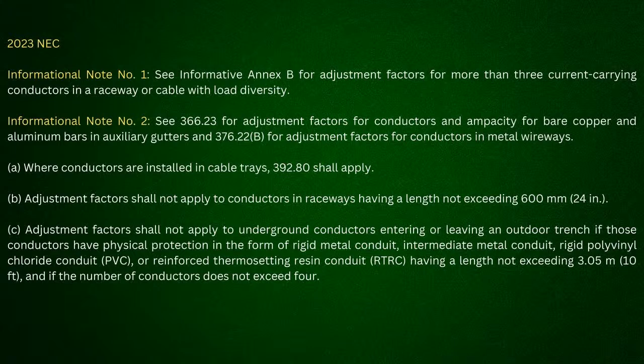But another good example, if I look at informational number 2, look what it refers to. 366.23, this is where we're dealing with auxiliary gutters. Well, if I look at an auxiliary gutter, I can put 30 current carrying conductors in there. And that's in an enclosure that is enclosed that doesn't allow for the escape of heat. But if I'm in a sleeve that actually allows for it, why the hell would I be able to do 30 here, but I'm in a sleeve that actually has for dispersion of heat? Now all of a sudden I've got to take and apply adjustment factors. That makes no sense. Oh, 100%.